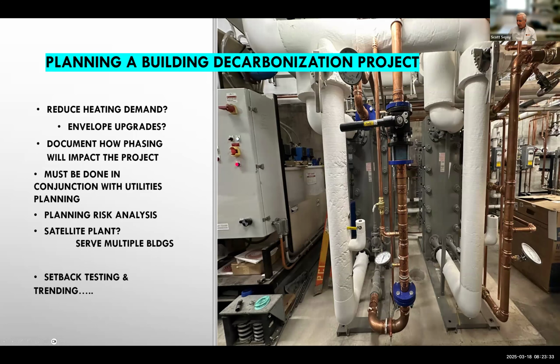Phasing, as we think of it, includes installing the new system, testing it as far as possible, and then when you're confident it is ready, remove the original equipment. For example, here are two domestic water plate and frame heat exchangers. The second one replaced the original unit after the first unit was installed and tested. Phasing pump installations also follows the scheme. Air units are converted 1 or 2 at a time, perhaps over a weekend shutdown. Perhaps controls need temporary services to test and commission new equipment.